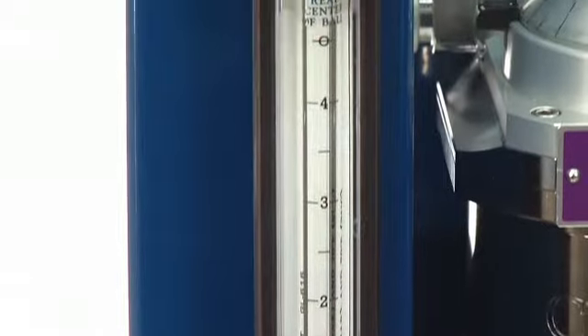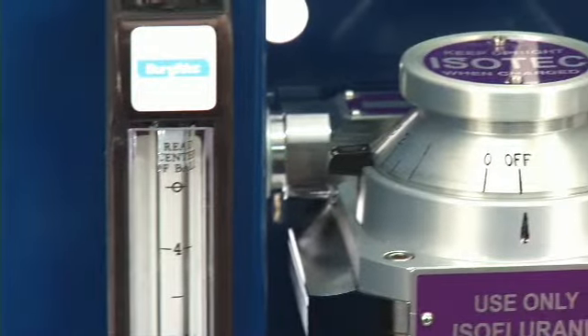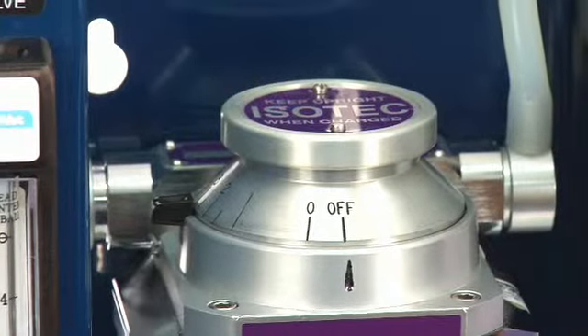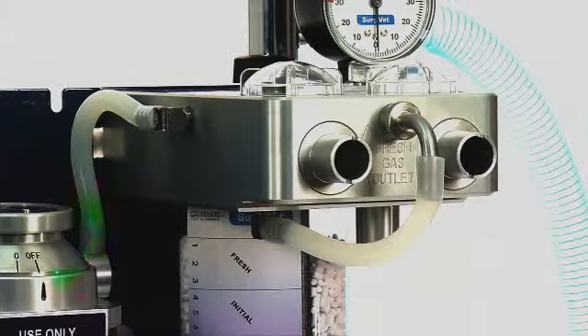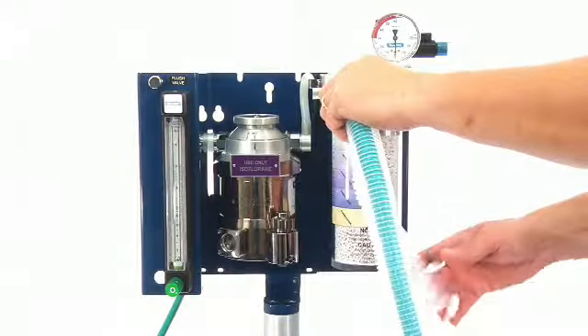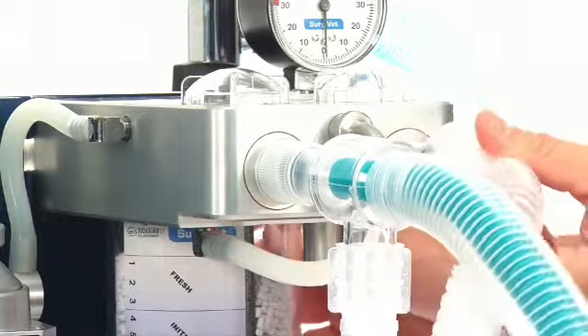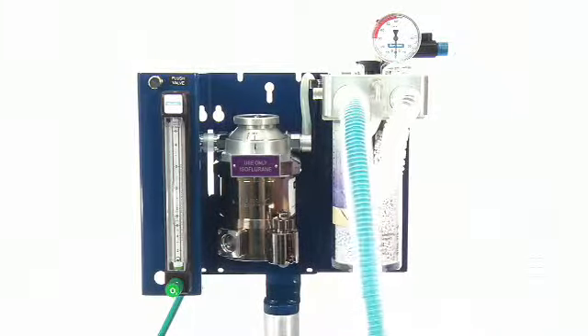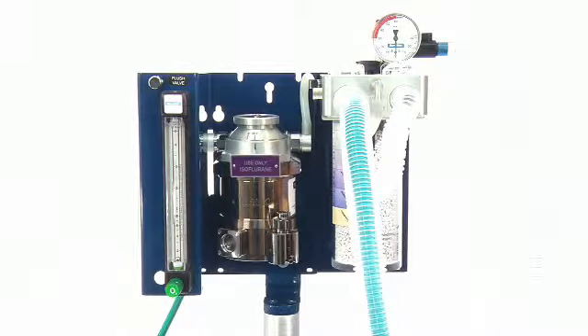Delivery gas from the flow meter is diverted into the vaporizer, creating the anesthetic gas mixture being delivered to the patient. Silicone tubing carries fresh gas from the vaporizer into the aluminum block and exits the fresh gas outlet, which is located between the inhalation and exhalation valves. The gas then re-enters the machine for rebreathing systems via the fresh gas inlet, which is located on the underside of the block. On the front of the machine sit the unidirectional inhalation and exhalation valves. This is where rebreathing patient circuits are attached.